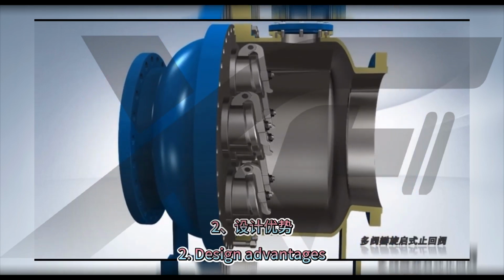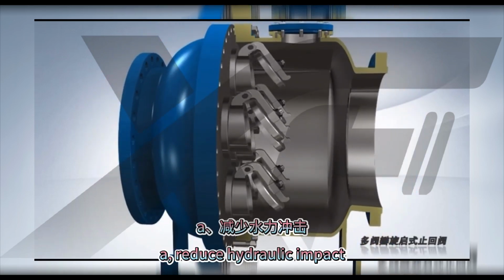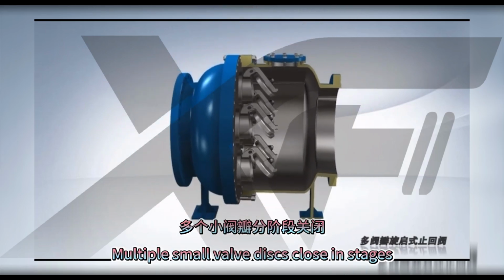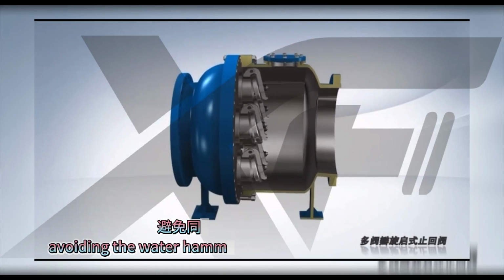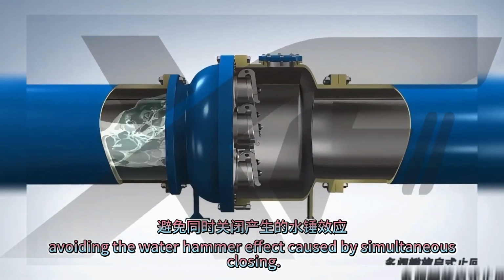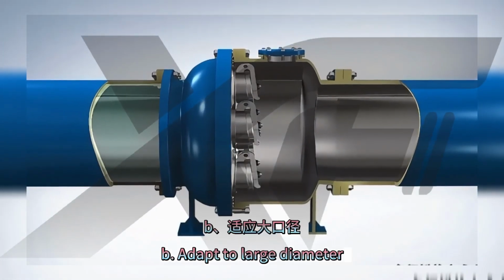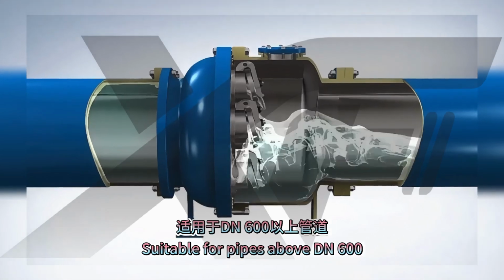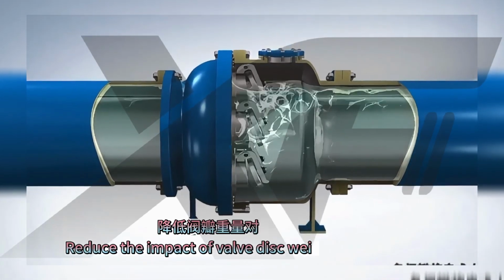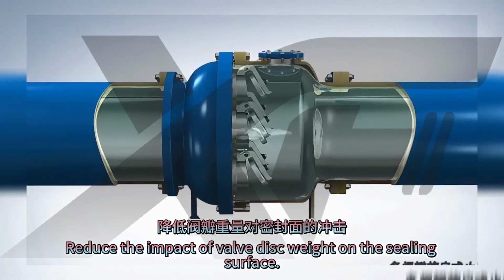2. Design advantages. A. Reduce hydraulic impact. Multiple small valve discs close in stages, avoiding the water hammer effect caused by simultaneous closing. B. Adapt to large diameter. Suitable for pipes above DN 600. Reduce the impact of valve disc weight on the sealing surface.